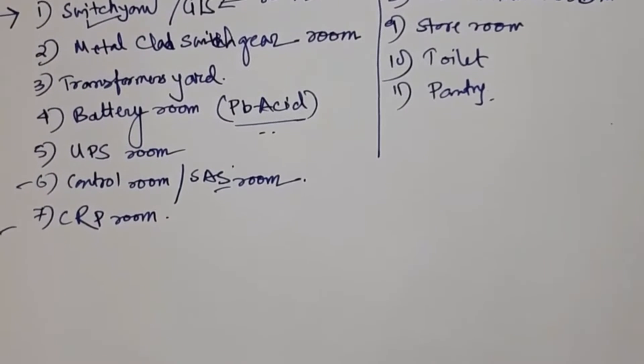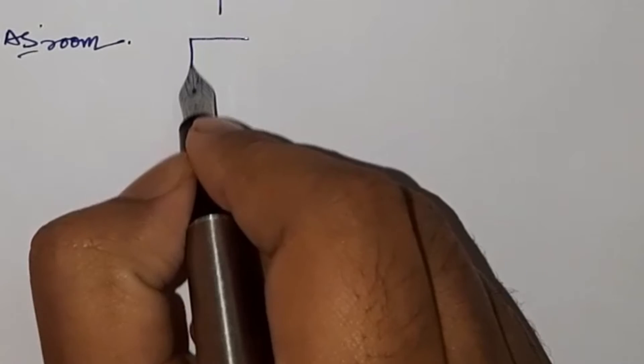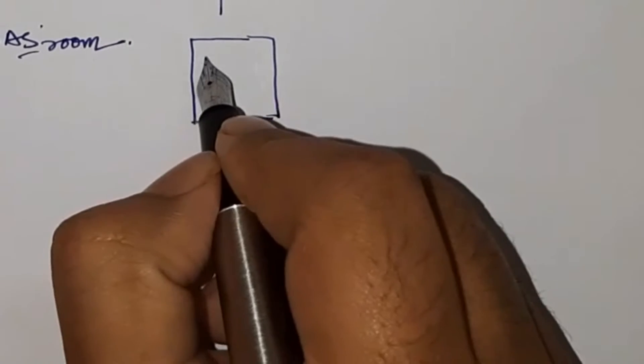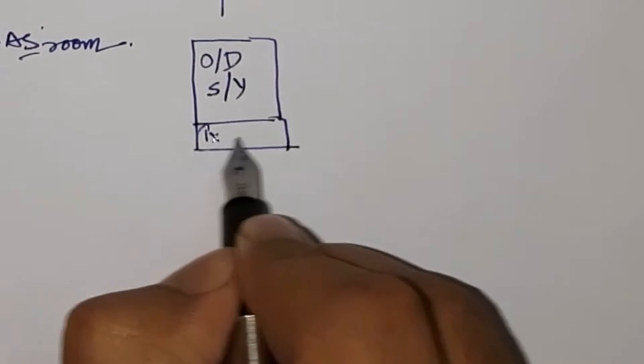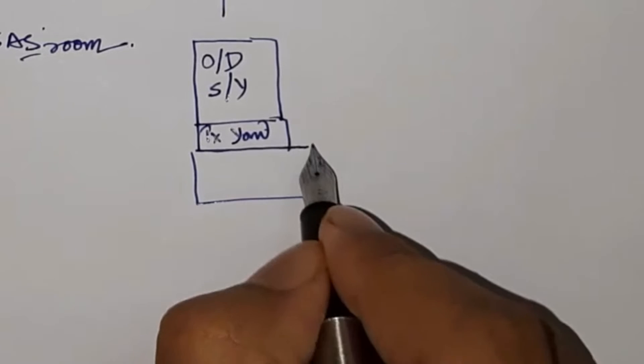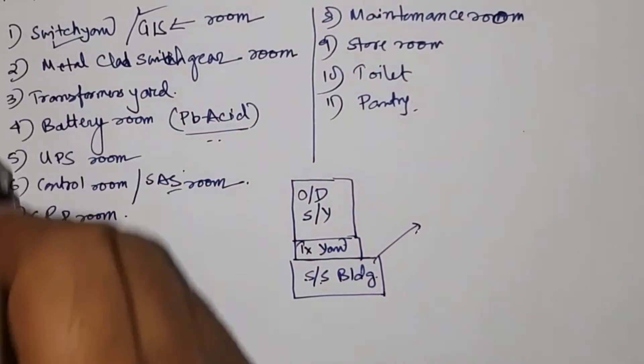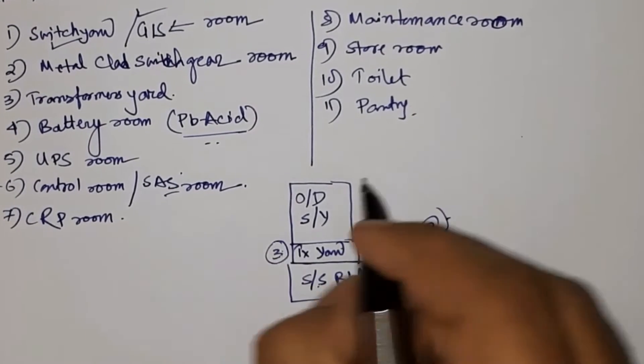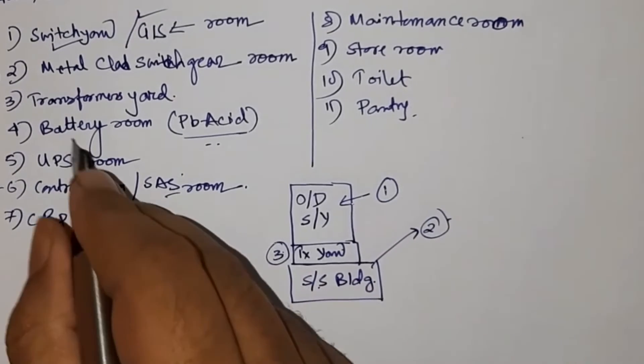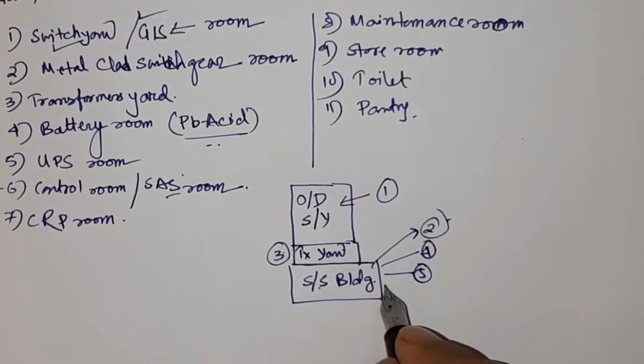Now if we try to draw an outline, let's consider a substation with a switchyard. Say this area is kept for the outdoor switchyard. Then here you can keep the transformer yard — all outdoor transformers go here. Then you consider a substation building. In this building you will have a switchgear room, transformer yard access, the switchyard area, and inside: battery room, UPS room, and control room.